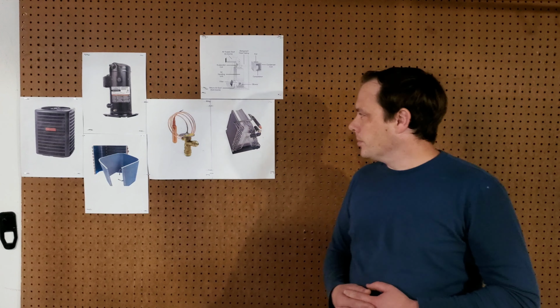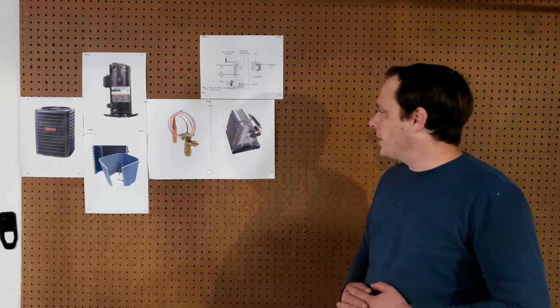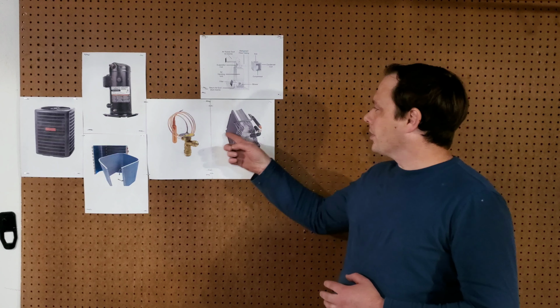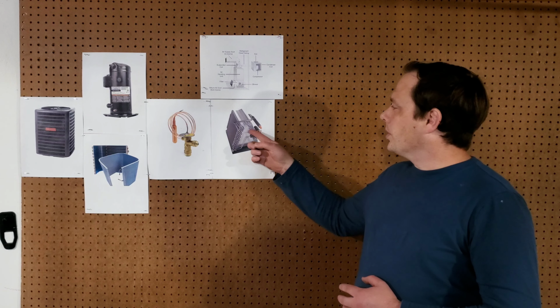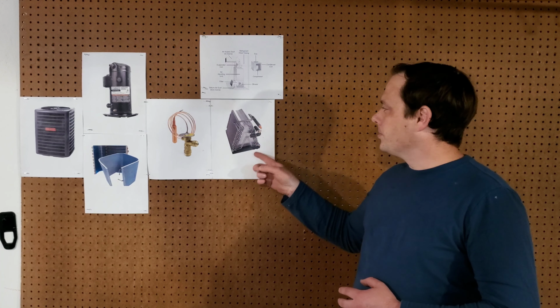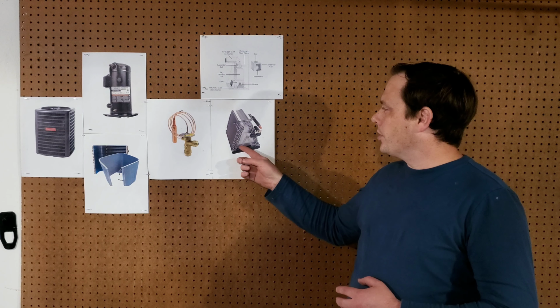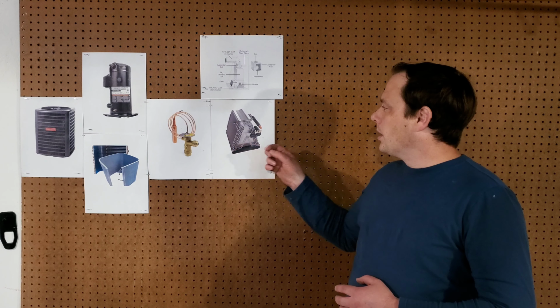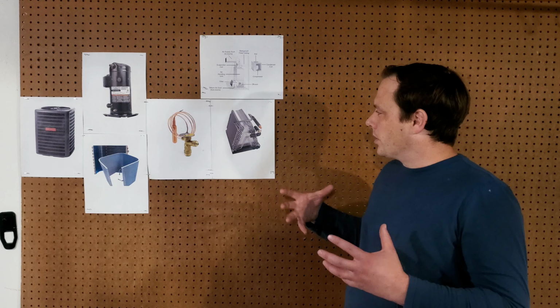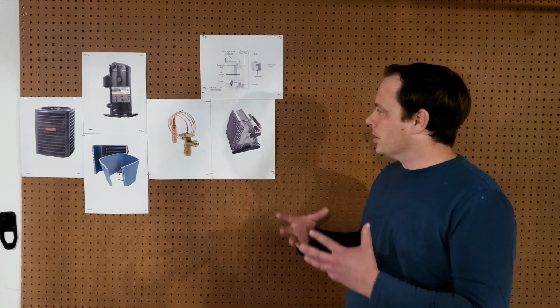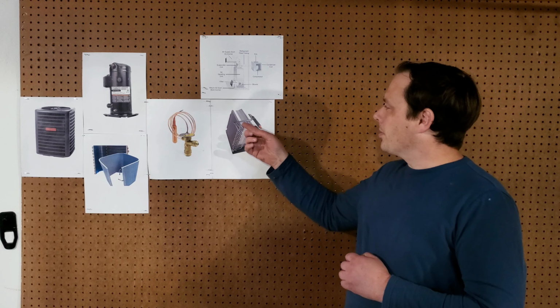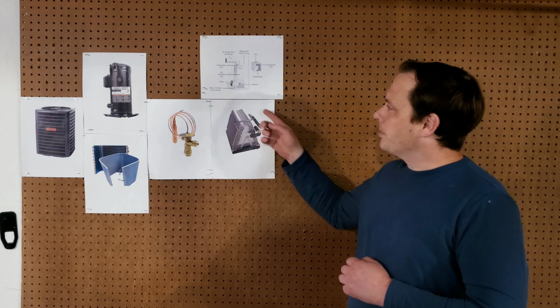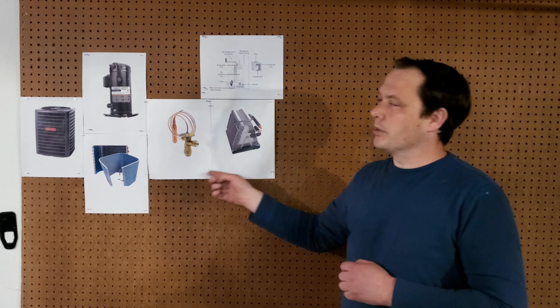In the evaporator coil, what's happening here is we have hot air traveling across the coil and cold air exiting the coil. On the liquid refrigerant side, we have liquid refrigerant being fed into the coil. That refrigerant at a cold temperature is now being boiled by the hot air, and vapor is sent out the top of the coil back to your compressor, and the cycle repeats itself.